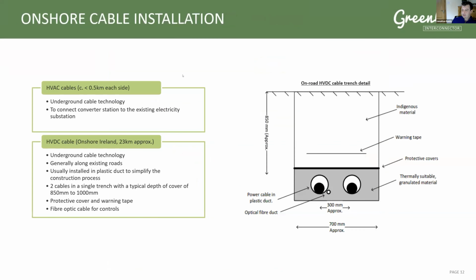However, this is what the onshore DC cable installation is going to look like. It's buried about 850 millimeters deep in ducts, and the two cables themselves will be buried about 300 millimeters apart from each other, generally along existing roads. Two cables in a single trench, with the protective cover and a fiber optic cable for the controls.